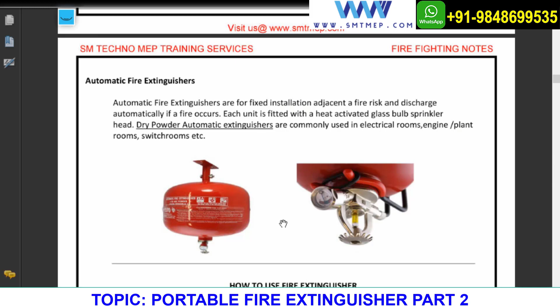So as per the color and the thermal rating, this will break and the compressed CO2 or the powder will come out on the affected area. So this is the automatic type, ceiling suspended type. Most commonly in the electrical room in the UAE you'll find this CO2 plus ABC automatic type. Or where manual operation is difficult, we can use this automatic type, like remote switchgear areas or remote areas. There is no manual operation. We can use this option.